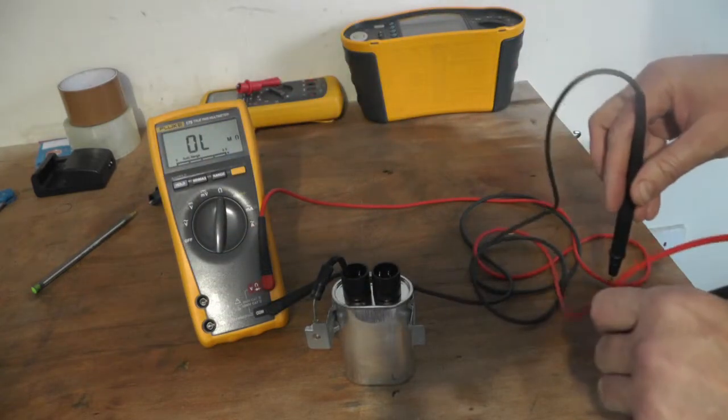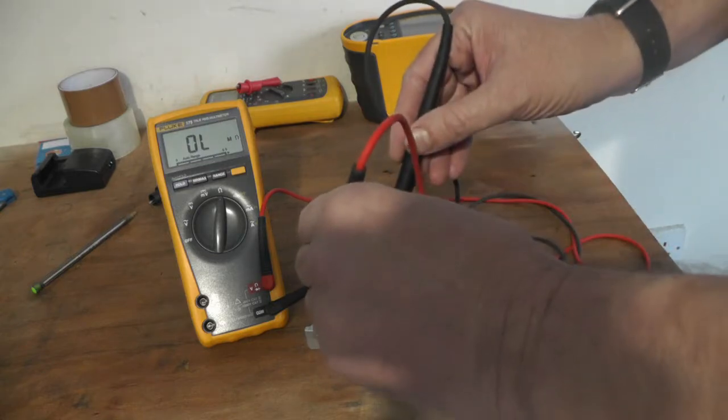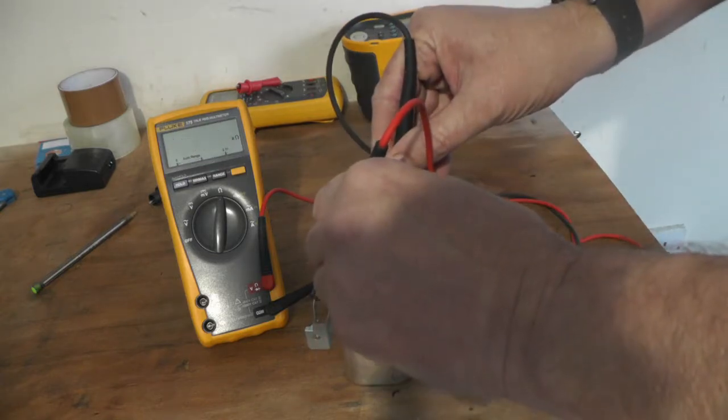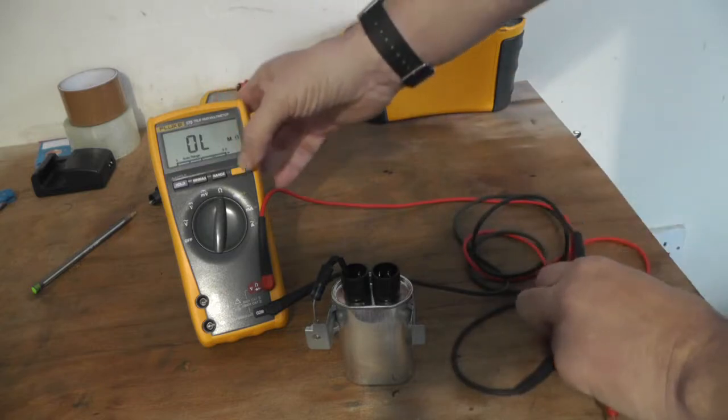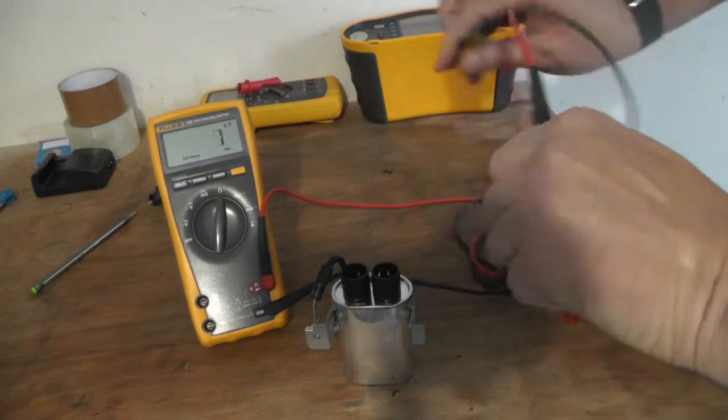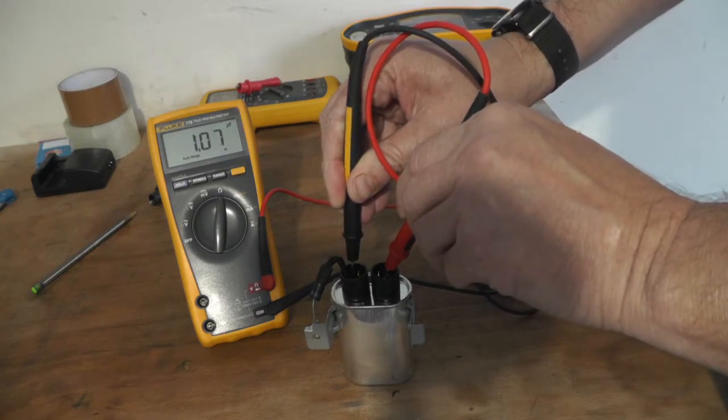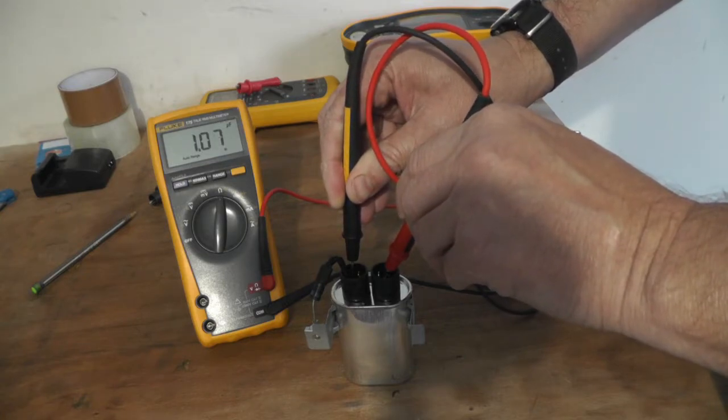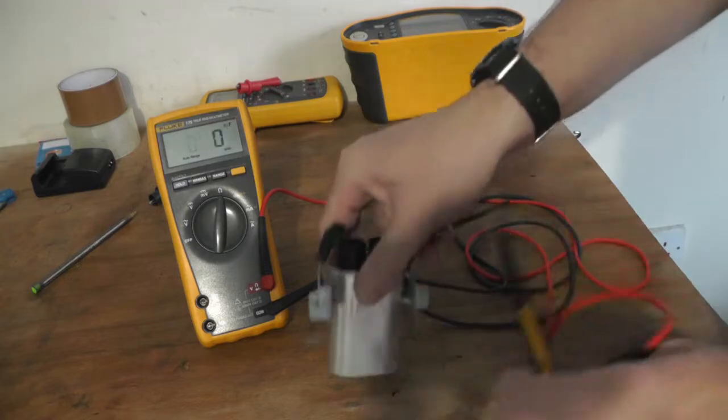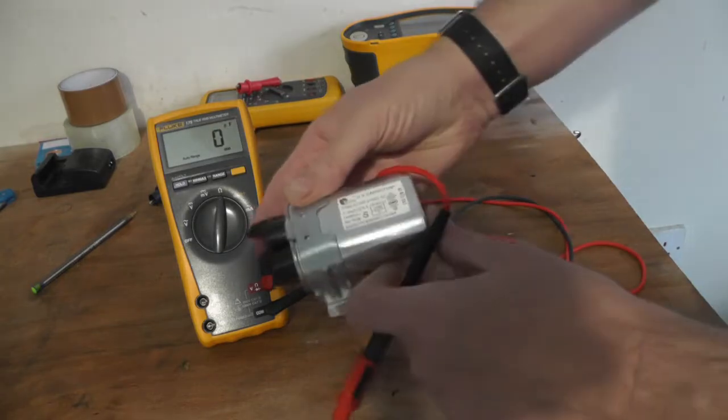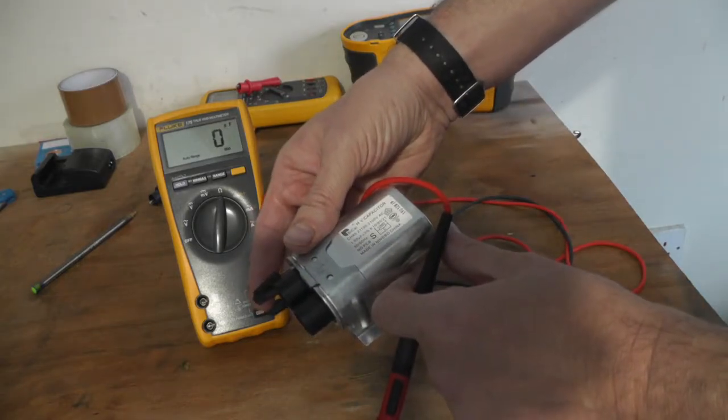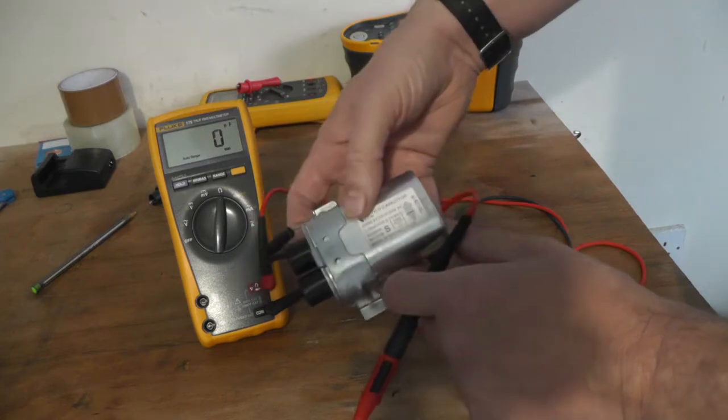Then I'm going to test it for capacitance. So 1.1 microfarad. It's supposed to be 1.05 so close.